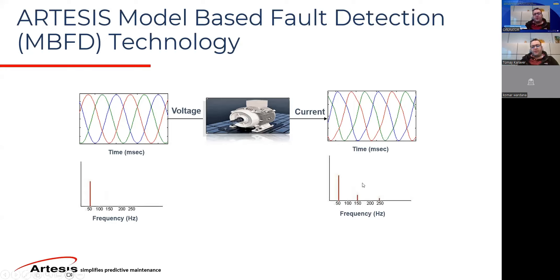We've seen these peaks in the frequency domain — the 50 Hz is our line frequency, which is normal. What we want is to only see the 50 Hz frequency here; if we see additional peaks, it suggests there is an issue. Whether it's small or big has to be evaluated by looking at the amplitudes, but the frequency suggests these are caused by the mechanical behavior of the rotating asset. So this is very important.